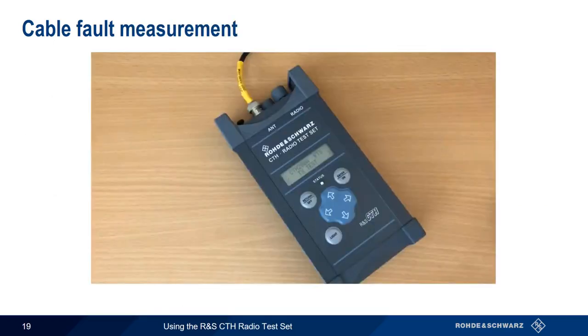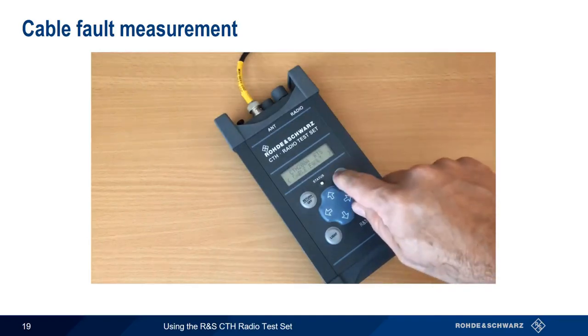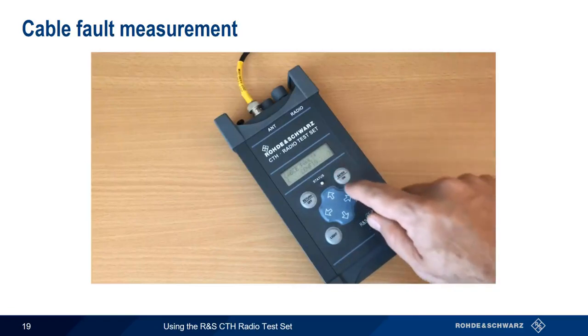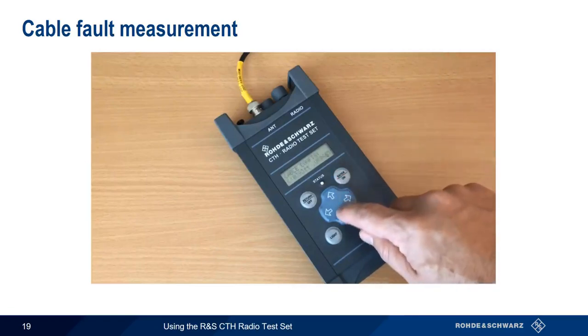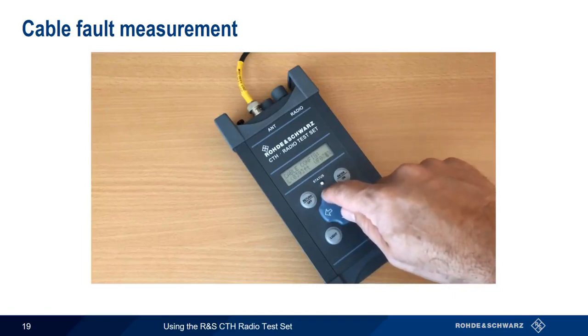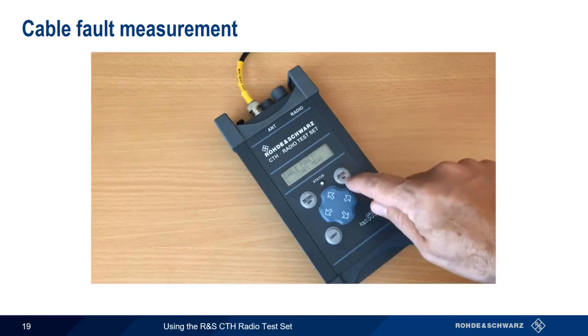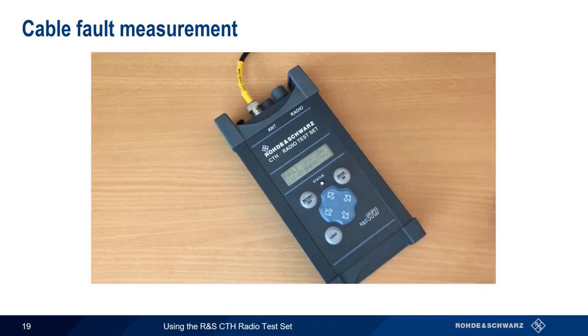When making cable fault measurements, the cable under test is connected to the CTH's antenna connector. After selecting Cable Fault Mode, we first need to configure our maximum cable length and velocity factor, using the up/down arrows to change numeric values. We then select Start Measurement, and the results are displayed automatically. Here we see a fault 29 feet from the CTH antenna connector. The up/down arrows can be used to scroll through any additional faults, if present.